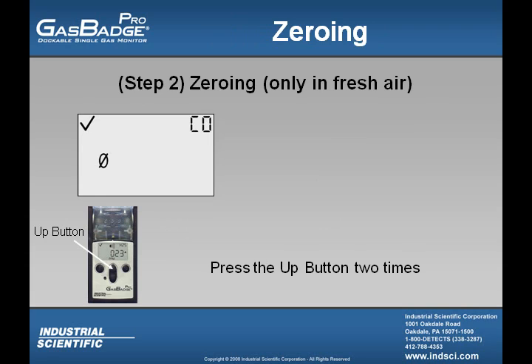Now, as I stated before, the user wants to zero the instrument, which is the second step of operation. Remember to only perform the zeroing function in a fresh air environment. And to zero the instrument, the user will have to press the up button 2 times. From there, they should see a 0 with a slash through it blinking.